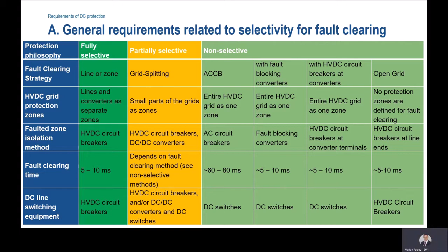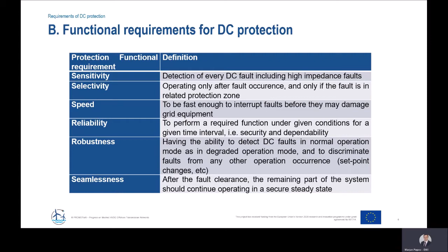Regarding the functional requirements for DC protection, because at this moment there is still no multi-terminal DC grid active in practice, we refer to the AC functional requirements, which are denoted as sensitivity, selectivity, speed, reliability, robustness, and seamlessness.